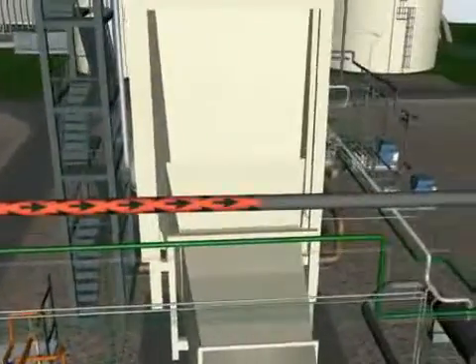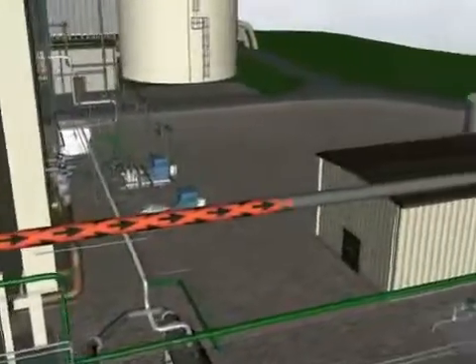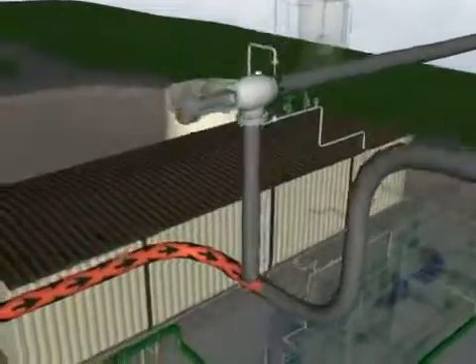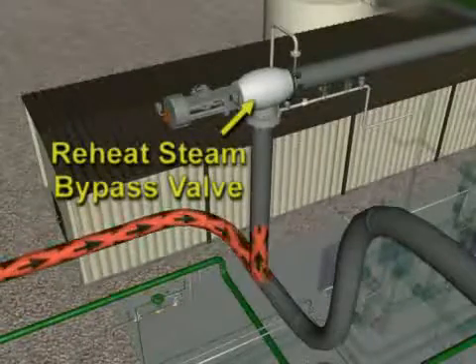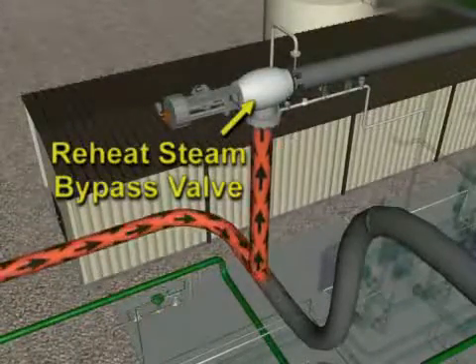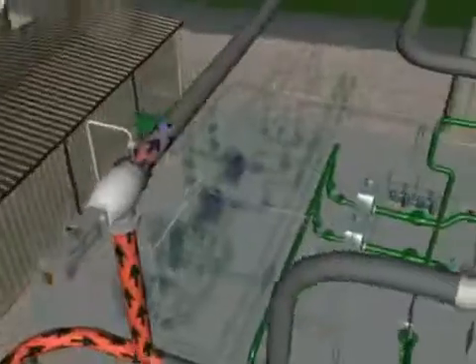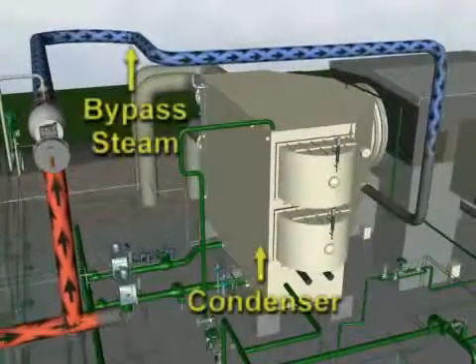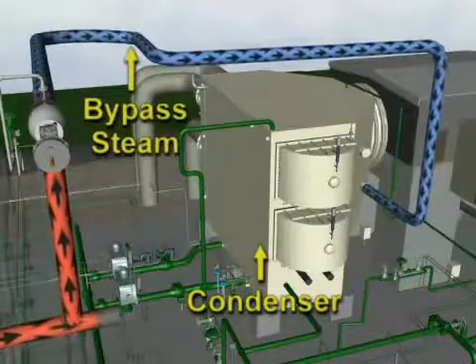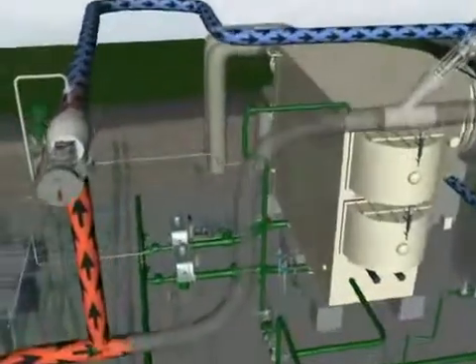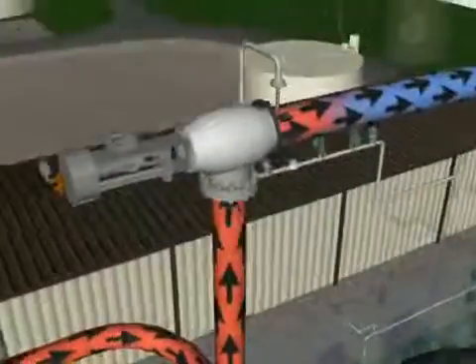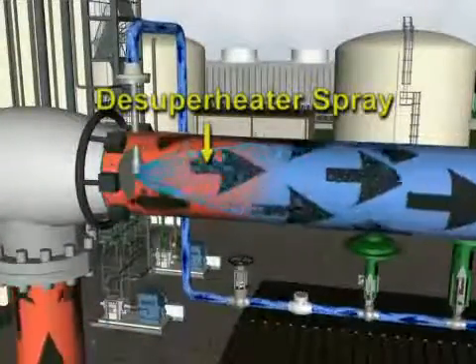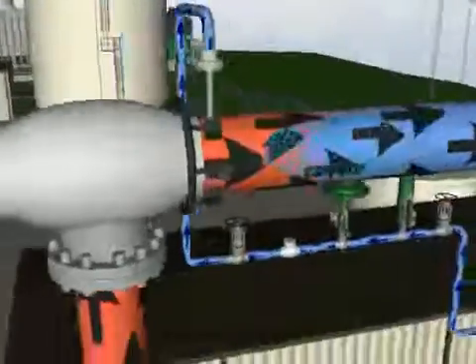Steam travels along the reheat steam line to the reheat steam bypass to condenser intersection. Under start-up or trip conditions, the steam may be bypassed to the condenser by means of a bypass valve. When the hot reheat bypass line is used, hot reheat steam is bypassed directly to the condenser. Steam directed to the condenser through the bypass valve is desuperheated to acceptable pressure and temperature levels for entry into the condenser.